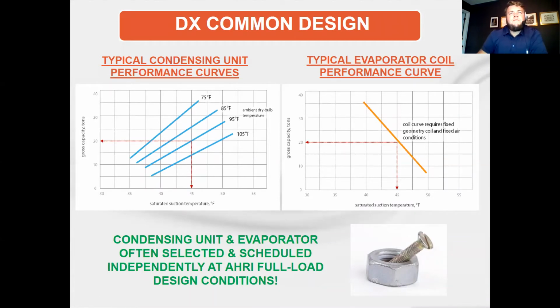Now on the right, you see the evaporator coil, and the opposite is true there. As the refrigerant temperature falls, the difference between the saturated suction temperature and the airstream increases, and therefore the heat transfer of the refrigerant increases. The capacity of the coil is greater with colder suction temperatures. So it's important that these two pieces fit together, not like our nut and bolt at the bottom of the screen. We want these pieces to be matched so that they work together.